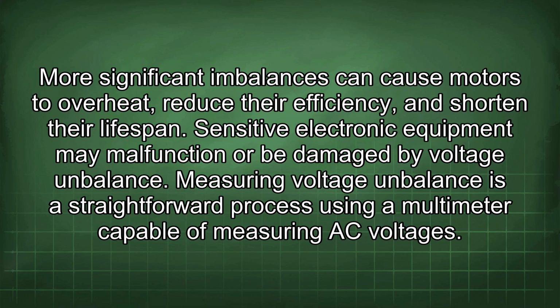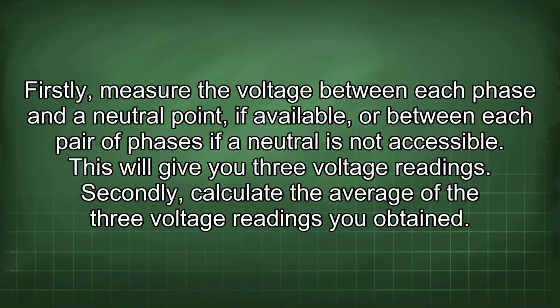Measuring voltage imbalance is a straightforward process using a multimeter capable of measuring AC voltages. Firstly, measure the voltage between each phase and a neutral point, if available, or between each pair of phases if a neutral is not accessible. This will give you 3 voltage readings. Secondly, calculate the average of the 3 voltage readings you obtained.